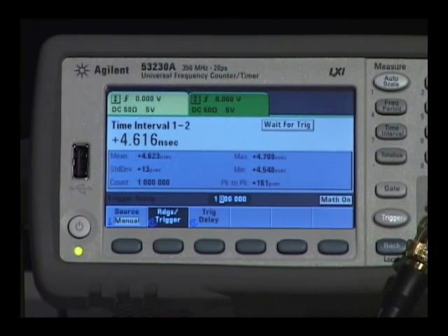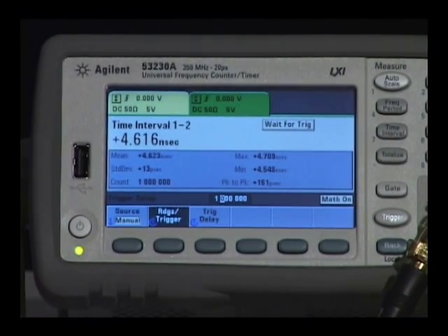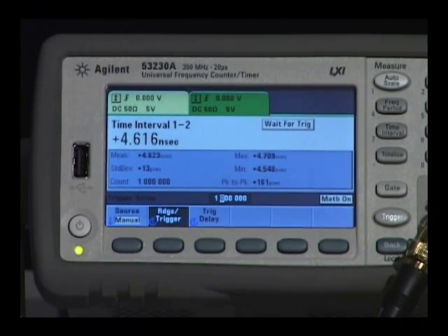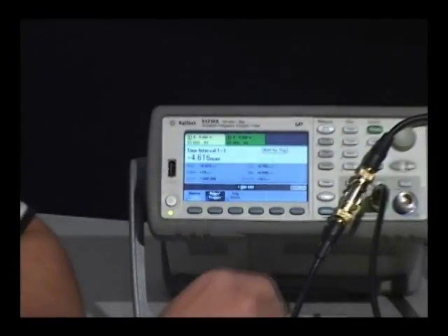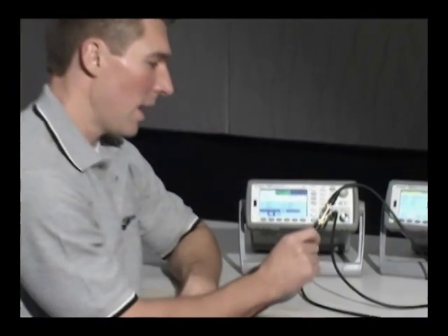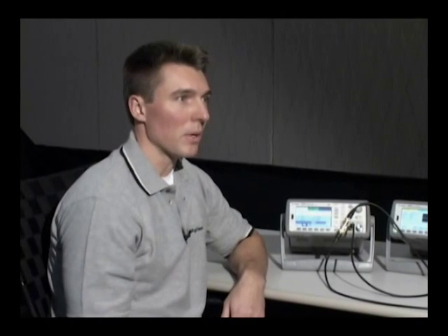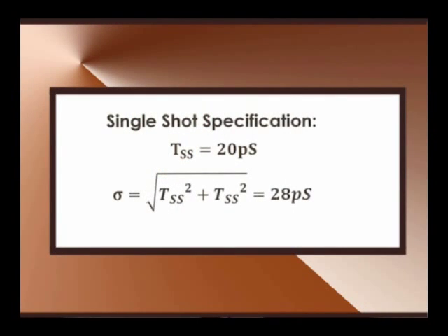But what's really important is the standard deviation — here we see it's 13 picoseconds. Now if we take the single shot resolution of channel one, which is 20 picoseconds, and find that we have the exact same resolution on channel two — another 20 picoseconds — to combine those you simply do a root sum square of 20 picoseconds with 20 picoseconds to arrive at the standard deviation spec of 28 picoseconds.